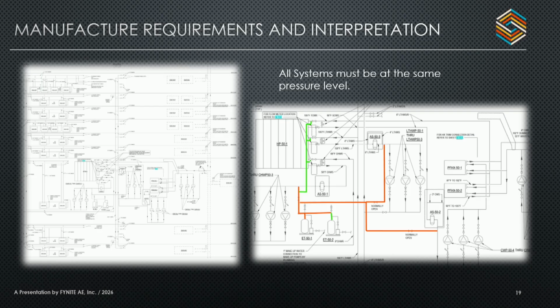So this equalizing line, which is required for equalization, because as the valves blend, all the water is mixing, and you can end up with a volumetric imbalance between the three headers, is required to allow water to bleed back across system to system. So what we're doing to resolve this issue is we're actually relocating that line from the pump suctions, which is shown in orange on the diagram, to the chiller inlet on each of the three headers, so that that same pressure is always on the headers and leads to equal pressure drop across the manifolds.